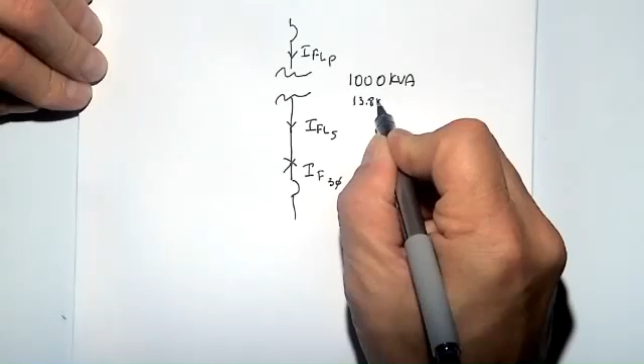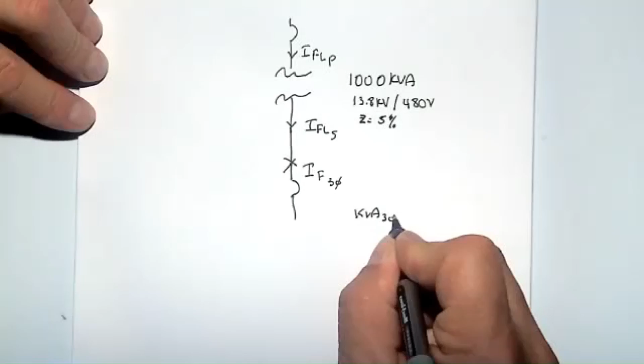Let's just use this as a very simple 1000 kVA, 13.8 kV primary to 480 volt secondary, impedance 5%. So we're going to go back to the equation that we started with and we talked about for three-phase power, which is kVA three-phase equals square root of 3, there's that square root of 3, kV line to line times I line. So if we solve for the current, I line equals kVA three-phase divided by square root of 3 divided by kV line to line. Then we just substitute in if we're on the primary or the secondary to calculate our current.